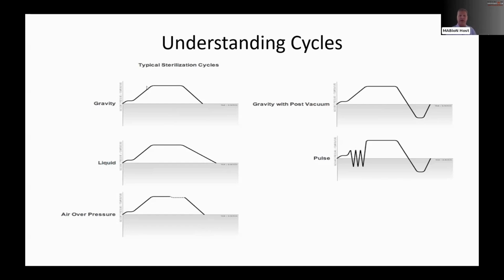You'll see that it's almost identical the way it starts with the gravity. It's going to gradually come up. It's going to reach the sterilization temperature. And then you're going to see the difference between here and here, the ramp down. A lot of autoclaves are designed to release the pressure as the temperature comes down at the same time. Generally, you're still going to get a little bit of boiling at the end of it, but it should ramp down. Your autoclave should ramp it down by 1/2 of a PSI per minute.